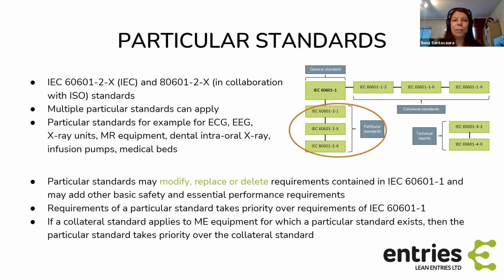Basically, if they have some specific properties for which it has been decided that the basic standard cannot really be applied fully, or if they need extra means of protection, that is why particular standards have been created for some of these devices. And they can modify, replace, or delete requirements from the main standard, and may add other basic safety and essential performance requirements as well. And the requirements of these particular standards also always take priority over requirements of the main standard. And if you have a collateral and a particular standard, then a particular standard also takes priority over the collateral standard.